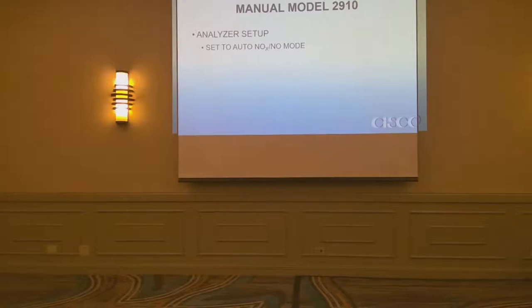How do you know the amount of NO2 that you produce? Good question. You'll be able to see that when we get to the chart, okay? This ozone lamp that we're typically using right now, on a 9 part per million NO cylinder of gas, we can get about 8 ppm of NO2 out. We might be able, on a higher concentration cylinder of gas, to get more out of it. But it's more than enough to test a 10 part per million full scale range analyzer.